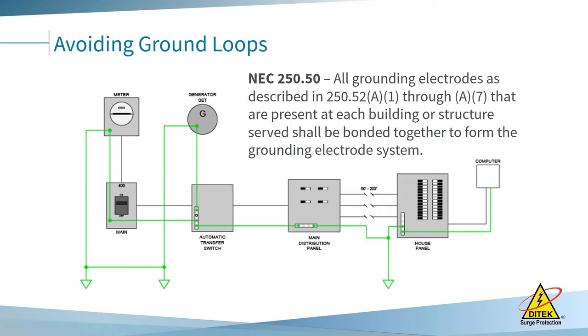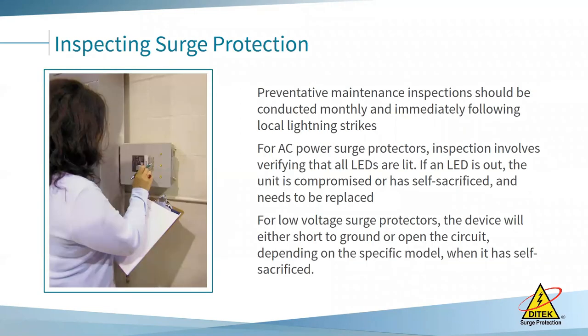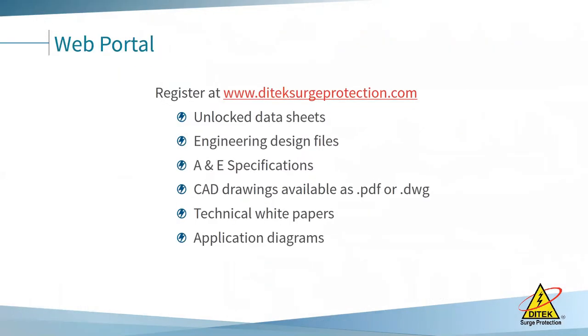For inspecting surge protection, the newer Ditek products use audible alarms and smart notifications. For legacy products, the LED is there for a reason — if the LED on the AC power surge protector is out, it needs to be replaced. Make sure your maintenance managers and operation techs are in the habit of checking the surge protector LEDs, because if a bad storm comes through and the LED isn't checked, the next surge will take out your equipment. For low-voltage protectors, the device will either short to ground or open the circuit when compromised — your first troubleshooting step should be to bypass the surge protector and see if the circuit comes back up.